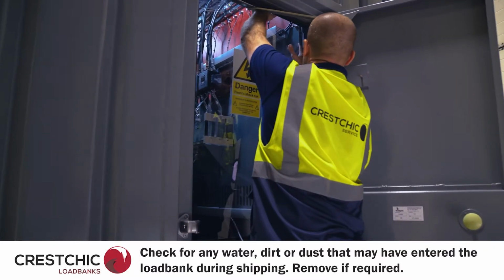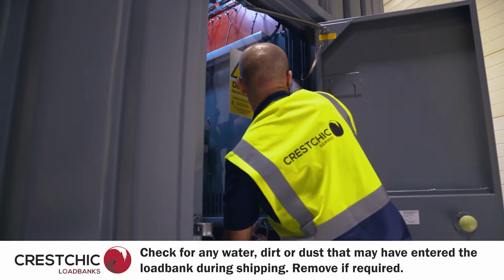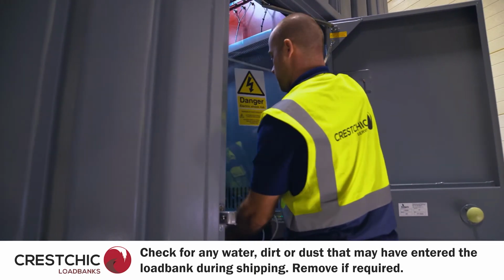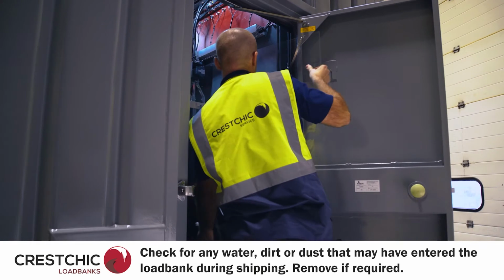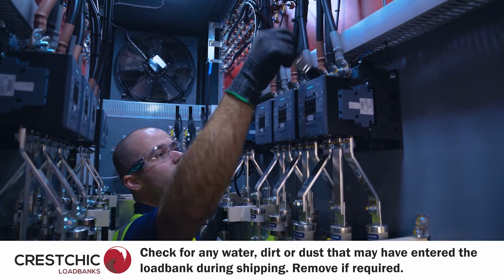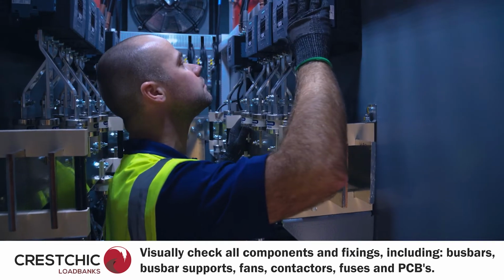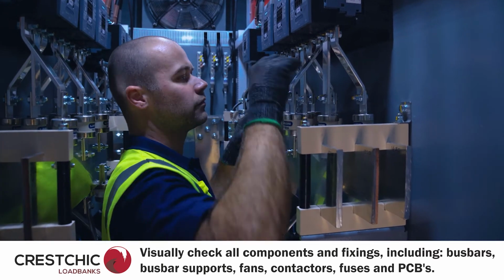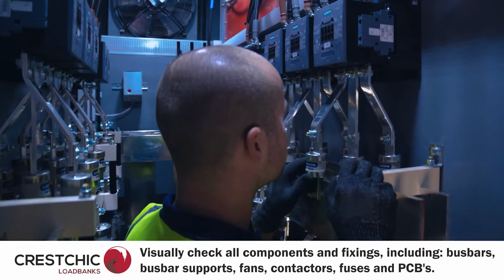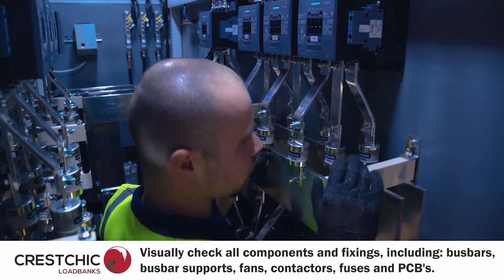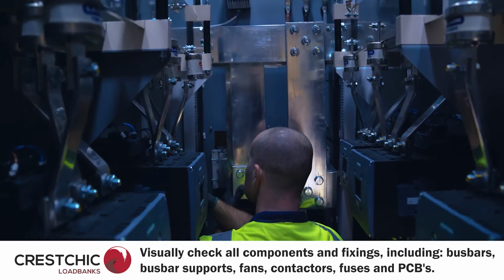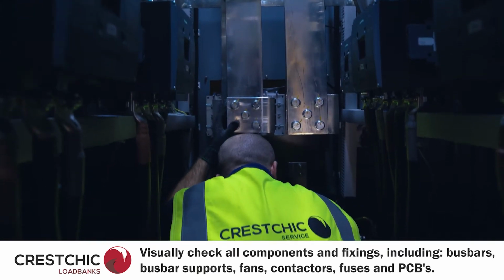As we have said, the load bank may have been on a long journey to get to you, so checking inside for any water or dust ingress is important. This should be removed if present. A visual check on all fixing and components should be completed. This includes, but is not limited to, fixing, bus bars, bus bar supports, fans, contactors, fuses and PCBs.